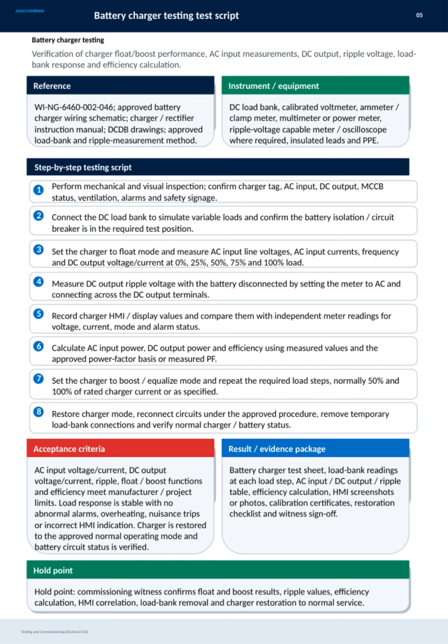Using these measurements, we calculate the AC input power, DC output power, and the overall efficiency of the charger, taking into account the power factor. The charger is then set to boost or equalize mode, and selected load steps are repeated, typically at 50% and 100% of rated current. Finally, the charger mode is restored to normal operation. Temporary load connections are removed, and the battery and charger statuses are verified.